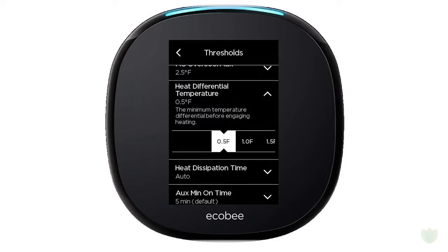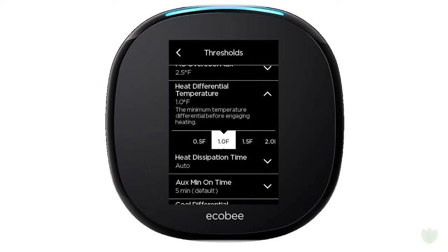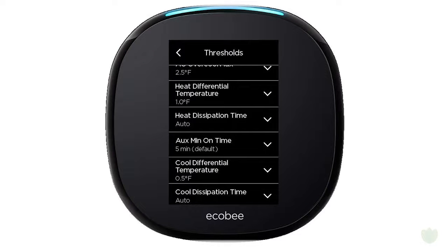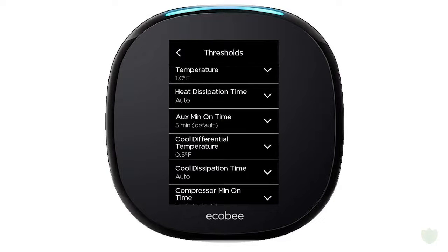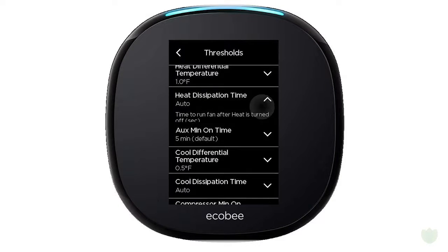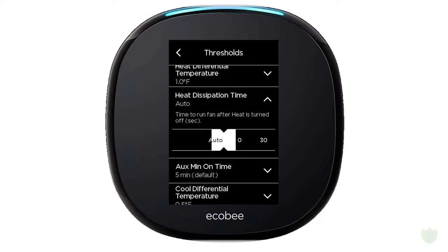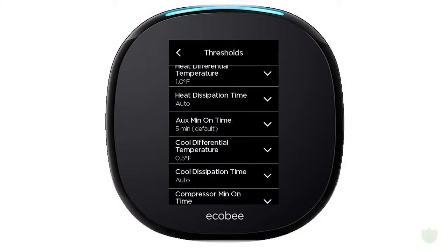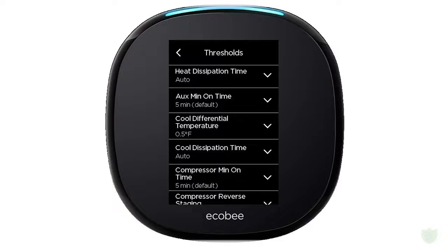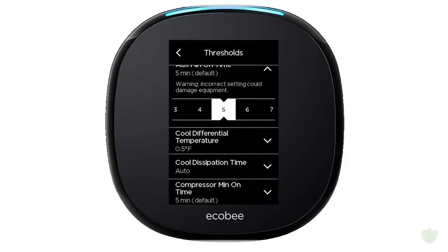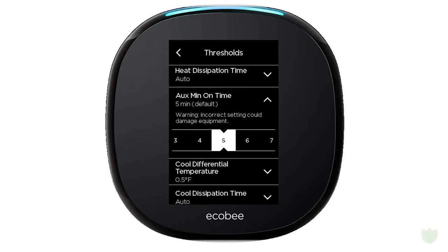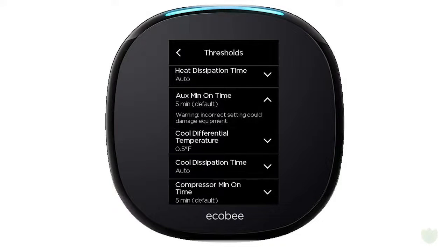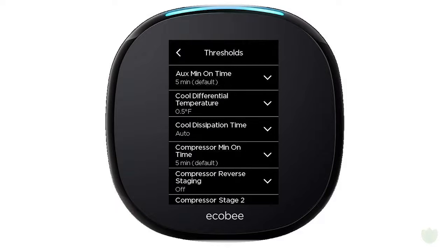You can adjust your differential. This is going to be the minimum differential before the heating kicks back on. So in between cycles, how far it's going to let that room temperature creep before the furnace runs again, or the heat pump. Dissipation time. So after the heat call is off, how long do you want that fan to keep running to keep that warm air flowing? Your auxiliary minimum on times, right? So you can adjust these. Going to default to 5. Again, want to be careful. Shouldn't probably be messing with this unless your contractor has advised you to.